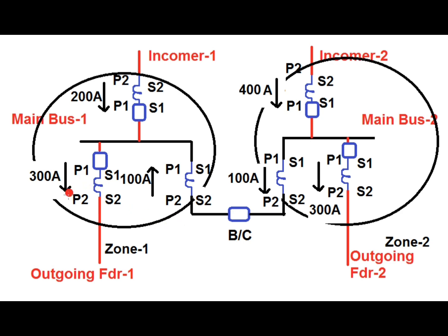Under normal load condition, outgoing feeder 1 and outgoing feeder 2 each have a load current of 300 amperes, while incomer 1 supplies 200 amperes and incomer 2 supplies 400 amperes. Since outgoing feeder 1 requires 300 amperes but incomer 1 only supplies 200 amperes, the remaining 100 amperes is supplied by incomer 2 via the bus coupler. Under normal condition, the zone 1 differential current is the sum of all CT currents connected to the zone 1 location — that is, incomer 1, outgoing feeder 1, and the bus coupler CT current.